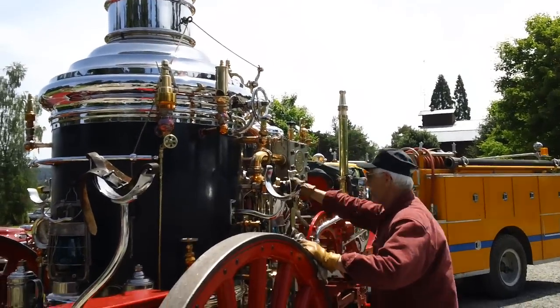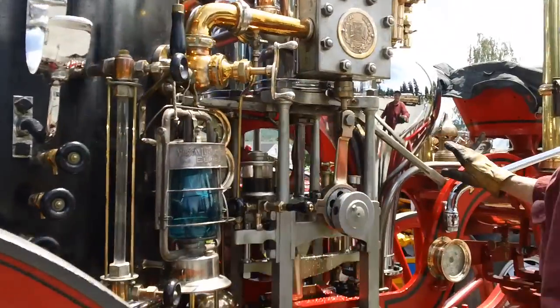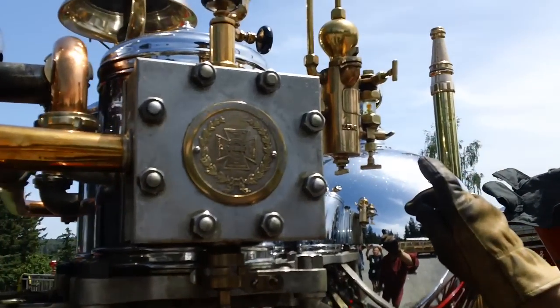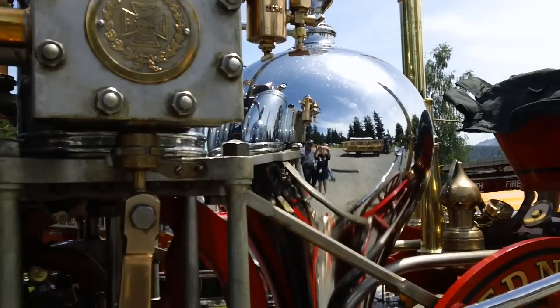They're going down to be on the pump. What he's doing is he's bringing the pressure up, he's checking the oil, making sure everything is oiled good. He's got a little oil bubble going up right there. Then he's checking all the valves, making sure there's no leaks.